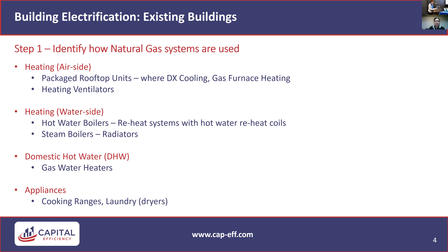Packaged rooftop units, on the left, that's what they look like. You can replace them pretty much equivalently with a heat pump that looks exactly like it, take the old one off and put the new one on. Or a better option is to go VRF, variable refrigerant flow, which gives more flexibility for simultaneous heating and cooling, with heat recovery options, and is a much more efficient option. It has its own challenges, like running refrigerant piping, but I'll give you a case study at the end showing VRF retrofits done in a practical way.